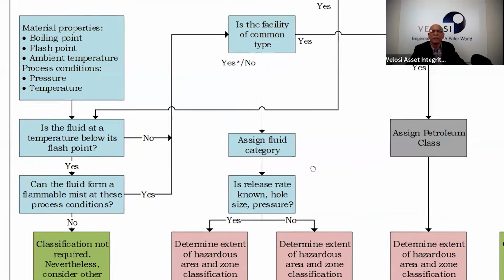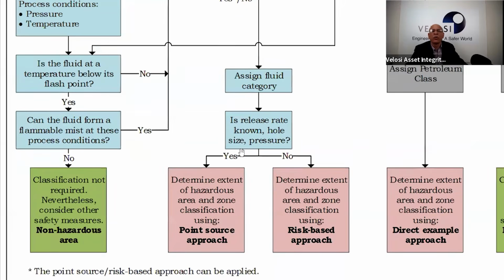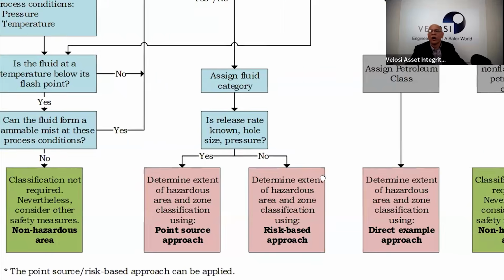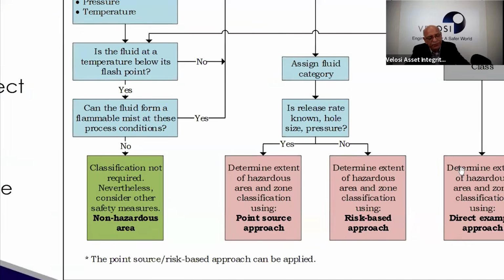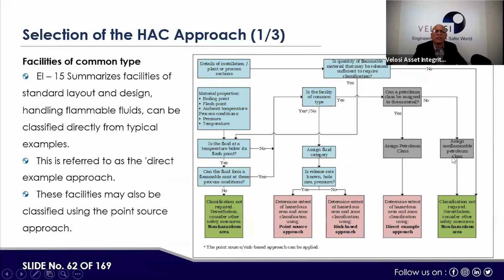Assign the fluid category. Is the release rate known, the hole size or pressure? Then determine the extent of the hazardous area and zone classification using the point source approach, or using the risk-based approach. So there are three approaches: point source, risk-based and direct example. The other two are how you can exclude. This is basically the methodology given, and normally we will be explaining more on the point source.